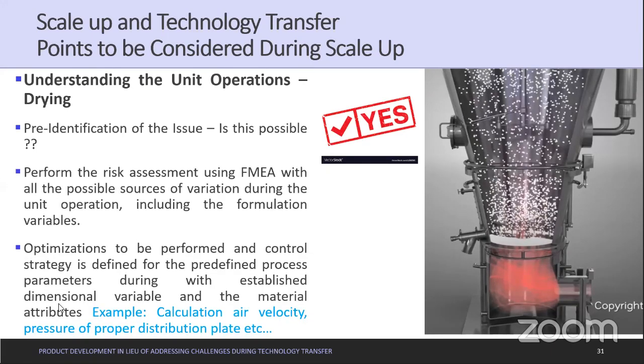That will be done during optimization and control strategy establishment of process variables. For example, for drying you will have process variables like calculation of air velocity or pressure of the proper distribution plate, etc. Once you do a risk assessment, identify a process variable, and convert that risk from a higher risk zone to a lower risk zone through various optimizations, you arrive at your process variables. You can then create a control strategy for your process variables, which needs to be monitored throughout your process.